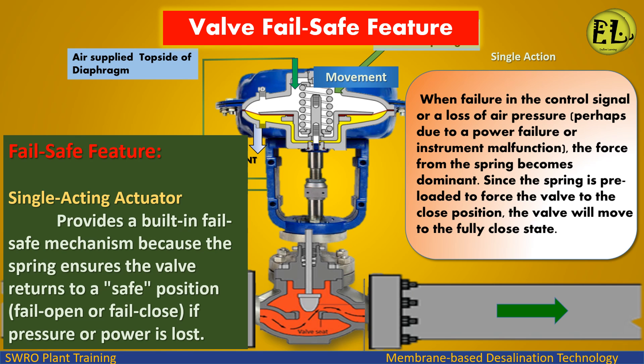Fail safe feature — single acting actuator: provides a built-in fail safe mechanism because the spring ensures the valve returns to a safe position — fail open or fail close — if pressure or power is lost.